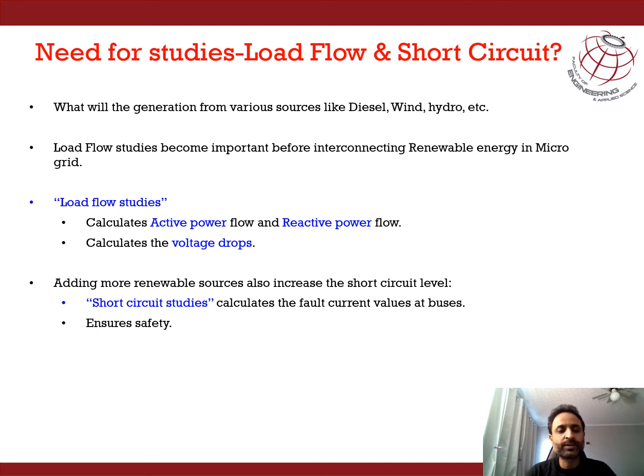Whenever a new generation is being added to an existing generation, then we need to see how the load will be distributed among the older conventional diesel generators and the wind turbines, and the new proposed system like the hydropower plant. As a result, we need to carry out what are called load flow studies. In the load flow study, we are able to calculate what will be the various active and reactive power flows from the various sources under different scenarios, and also what will be the voltage drops at various buses.